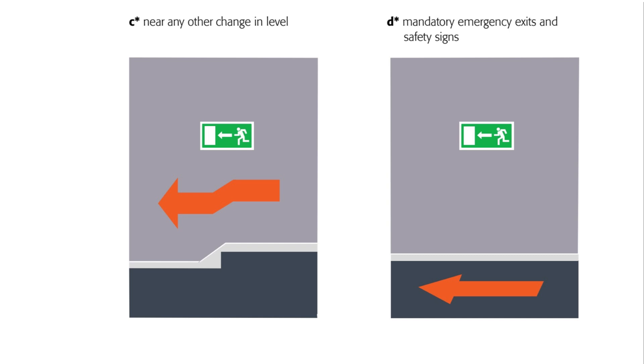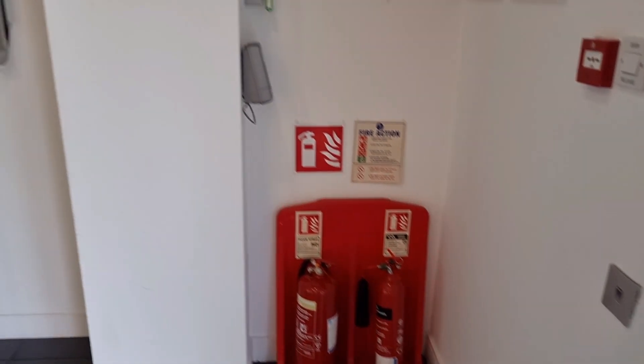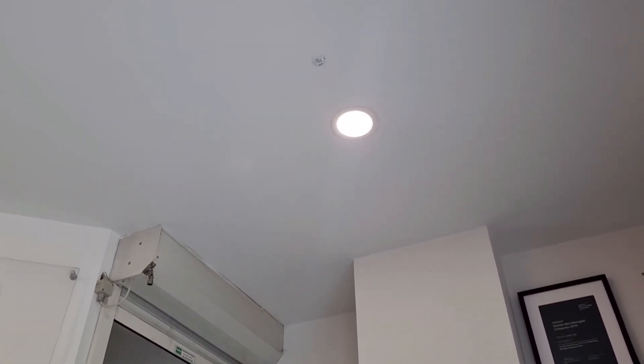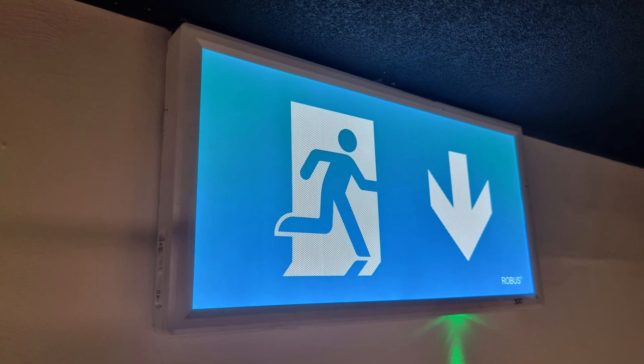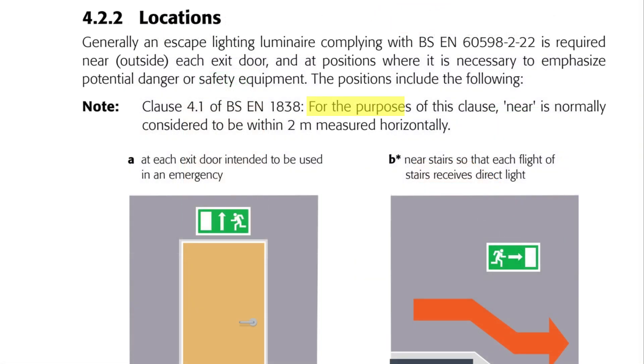Next up is mandatory emergency exits and safety signs. The example given is a direction of travel sign, but this could include signs to safety equipment like first aid locations or firefighting equipment. These probably wouldn't have their own internal illumination so might require an emergency light fitting nearby. We also have the option for glow-in-the-dark safety signs, but quite frankly we're electricians — we're going to prefer a nice light fitting. It's worth noting that for the purposes of this clause, 'near' means two metres.